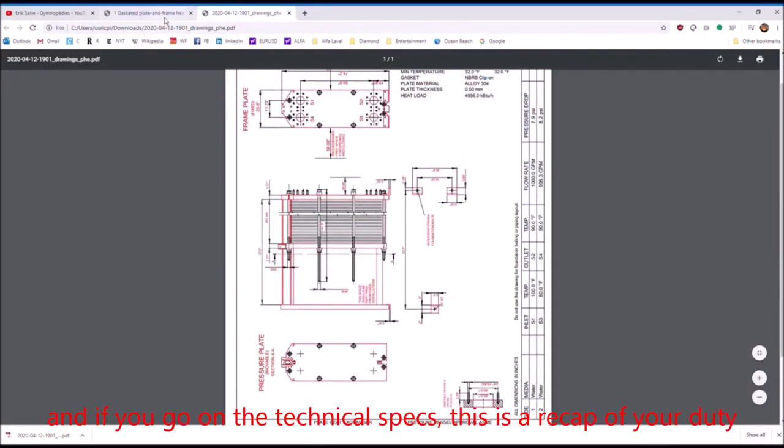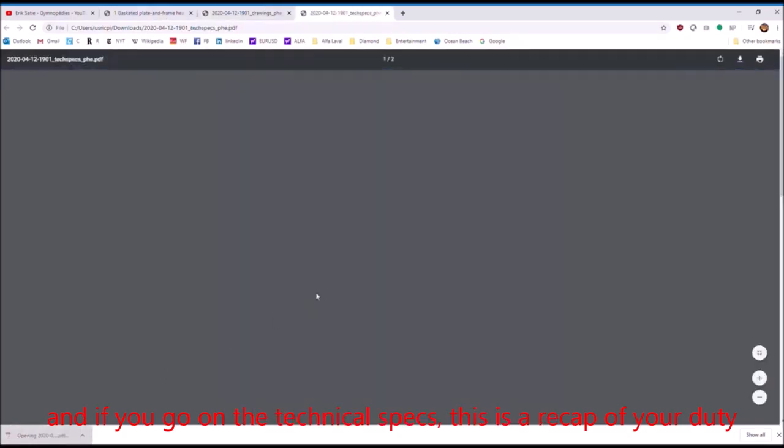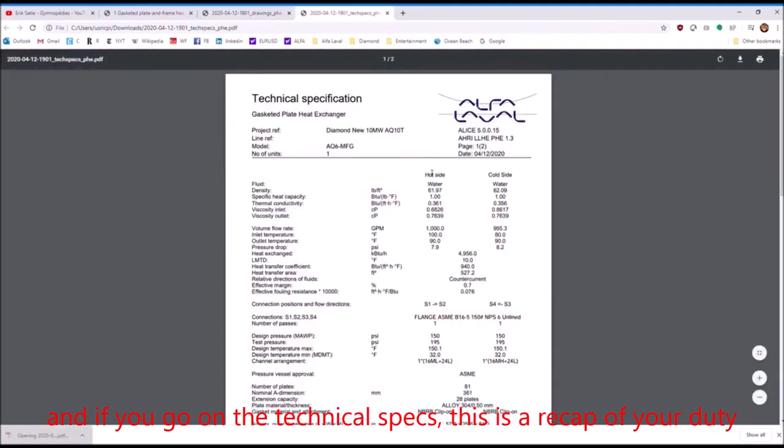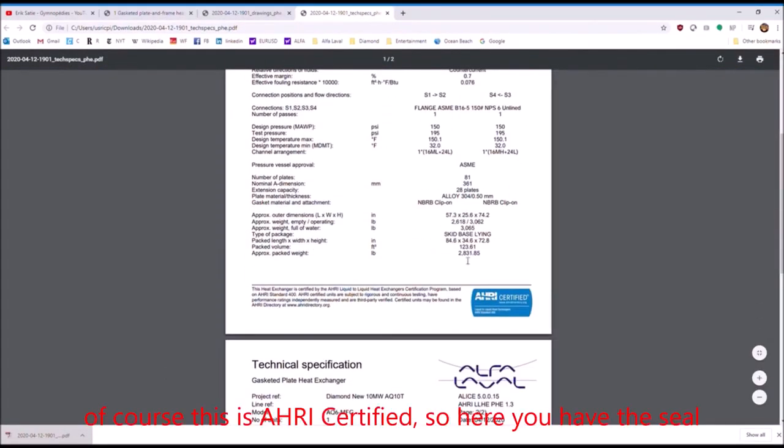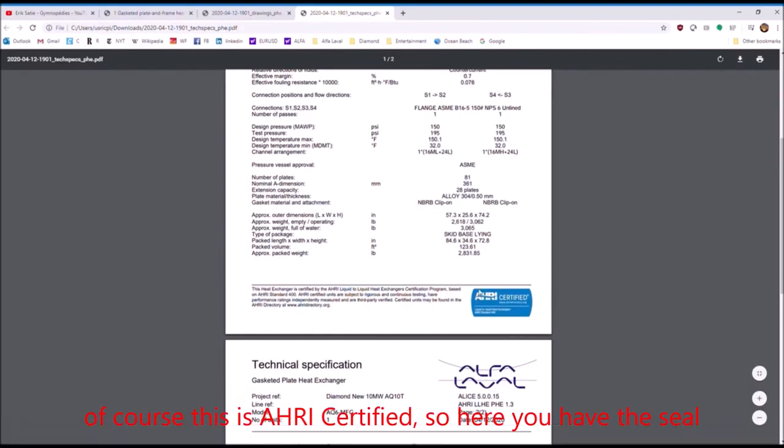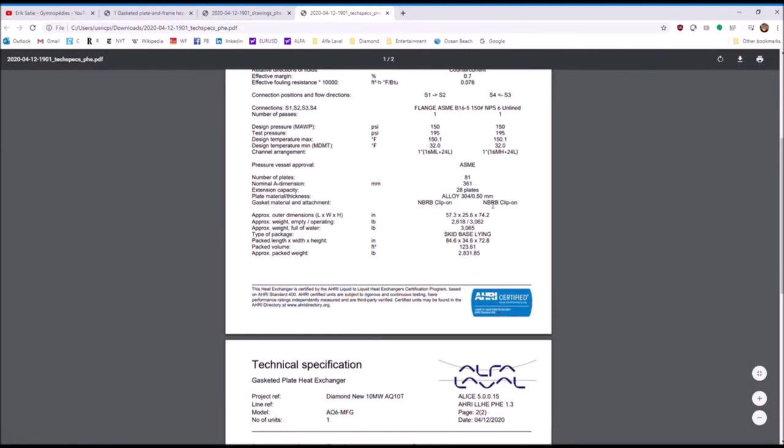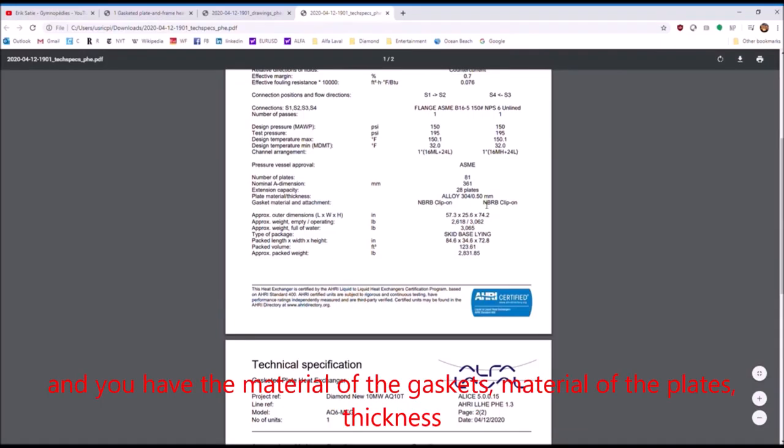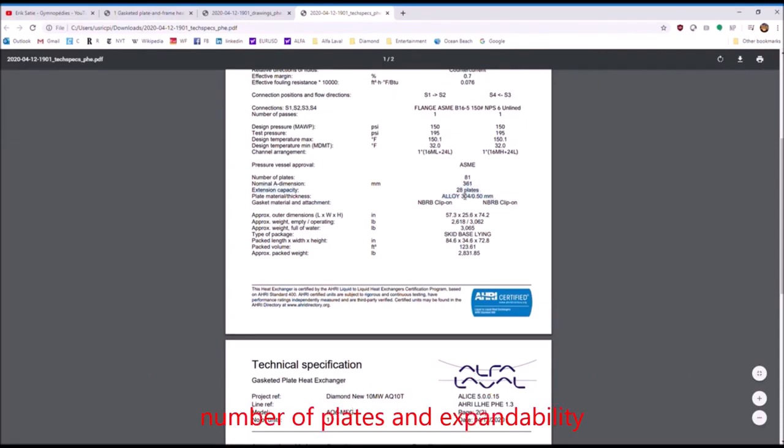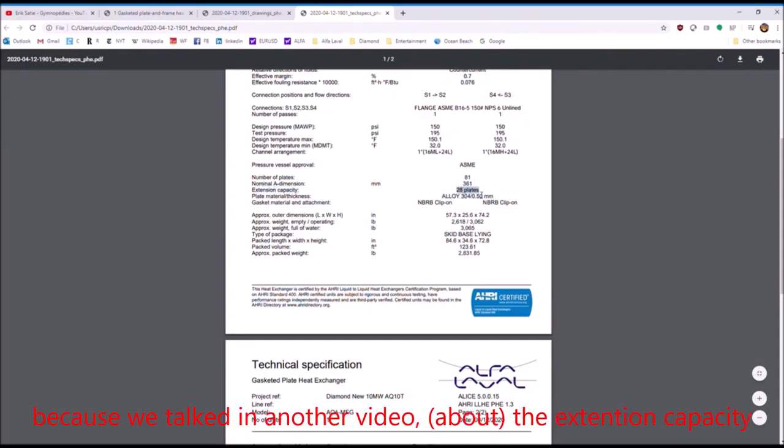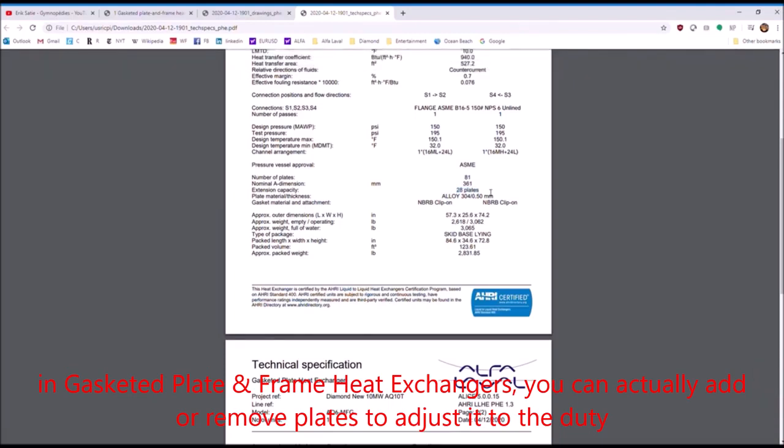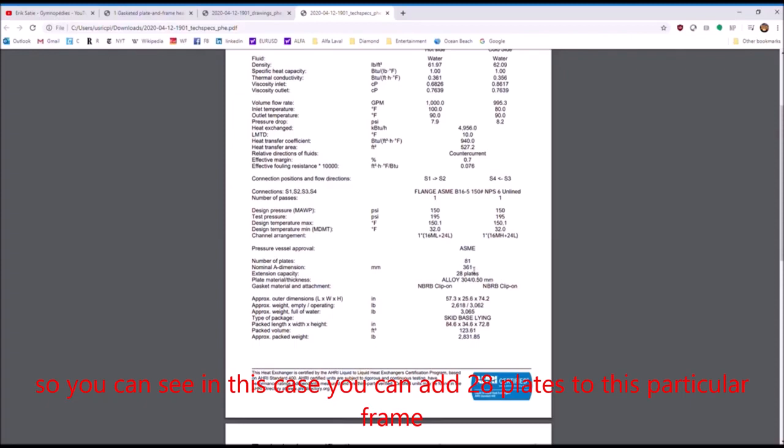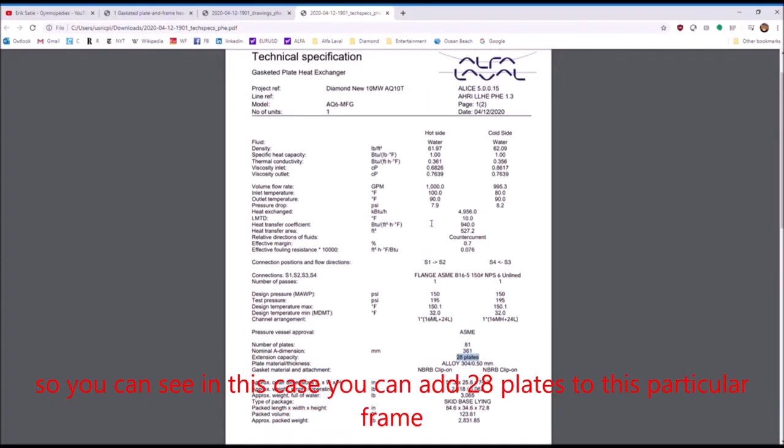And if you go on the technical specs, this is a recap of your duty. Of course, this is AHRI certified. So here you have the seal and you have the material of the gaskets, the material of the plates, thickness, number of plates, and expandability. Because we talked in a video about the extension capacity in gasketed plate and frame heat exchangers, you can actually add or remove plates to adjust it to the duty. So you can see in this case, you can add 28 plates to this particular frame.